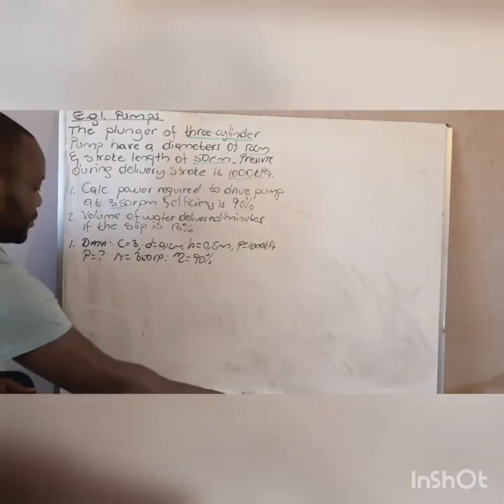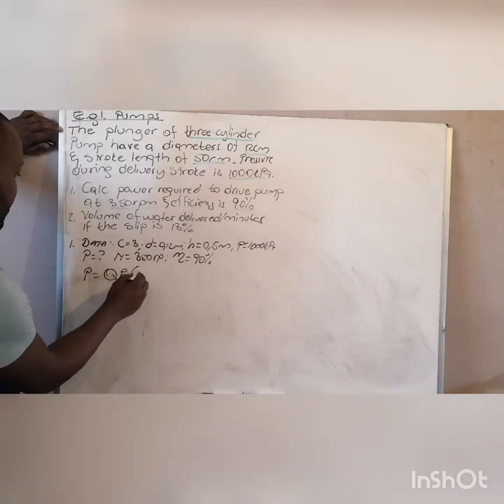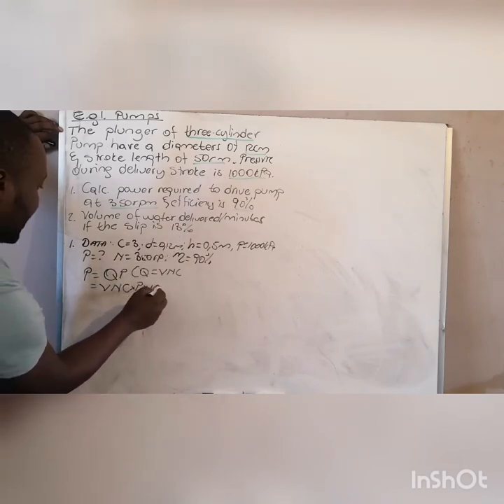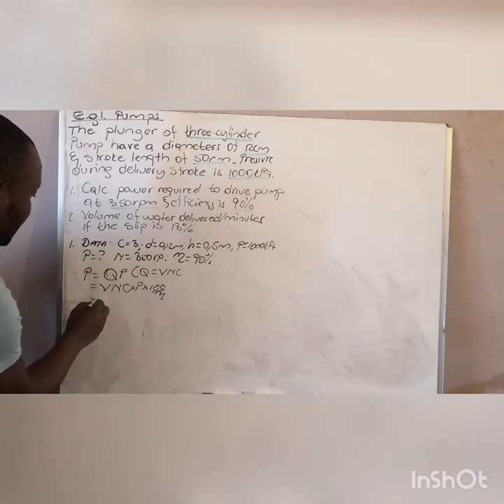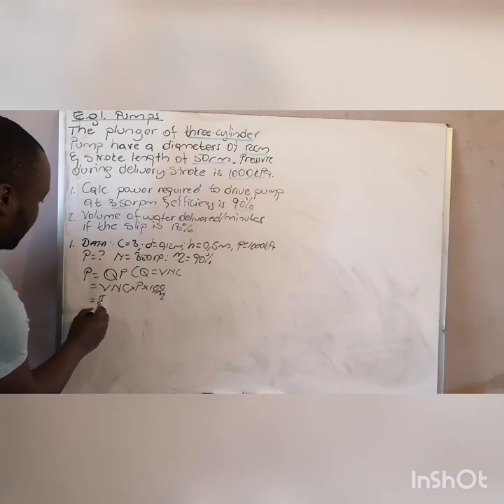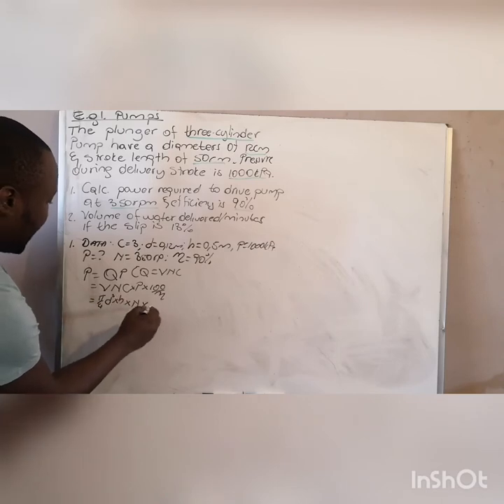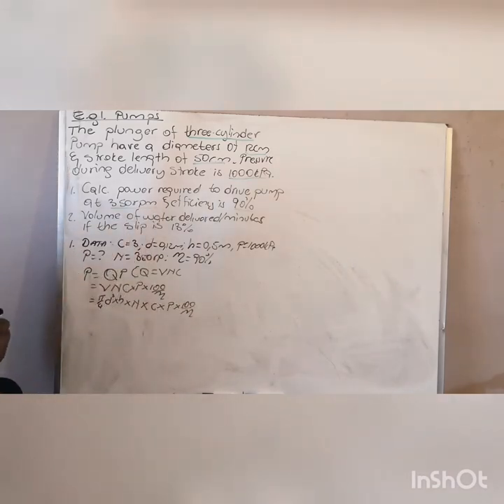From the equation I gave you, power equals the quantity of liquid delivered times pressure. Your Q is V times N times C, so power equals V times N times C times pressure times 100 over efficiency. Your volume is area times height, which is π/4 times d squared times the stroke length h. So the full equation becomes: (π/4 × d² × h) × N × C × pressure × 100 over efficiency.